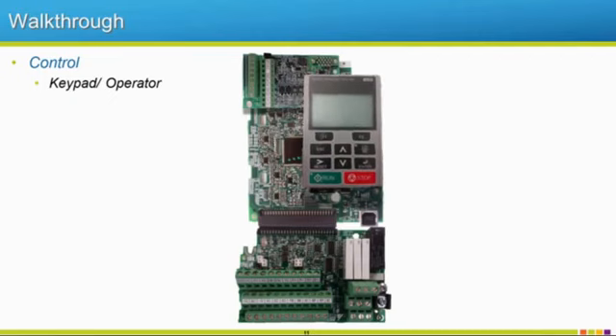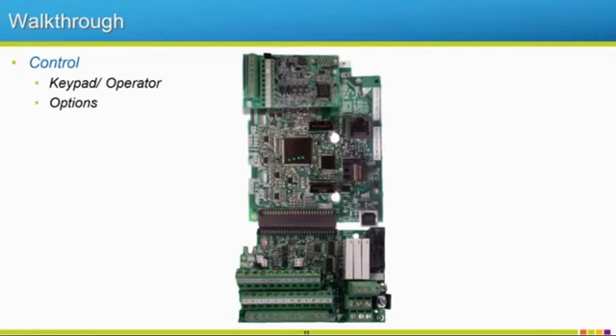You also have the ability to run from your keypad if you would want to, or run from, which we'll talk about in a second, maybe our terminal board and receive a 4 to 20 signal or 0 to 10 signal for our frequency reference, so telling us what speed we would like to run at. Some options could be available with our drive. This one just happens to have an encoder card located on it.